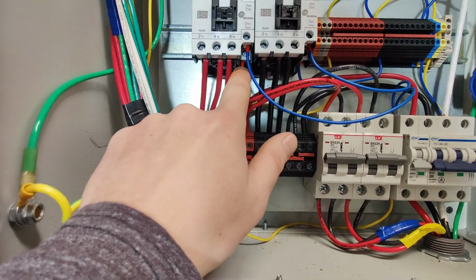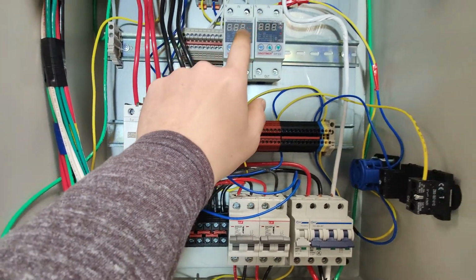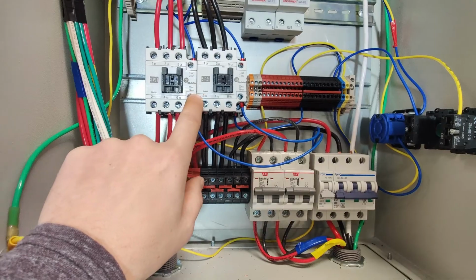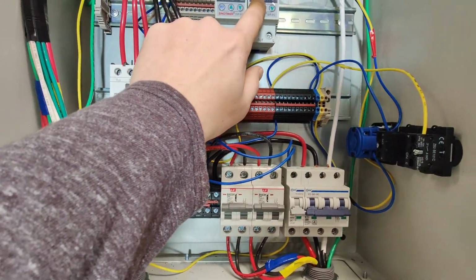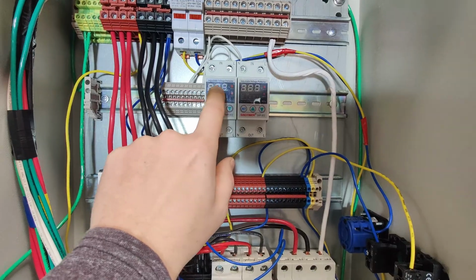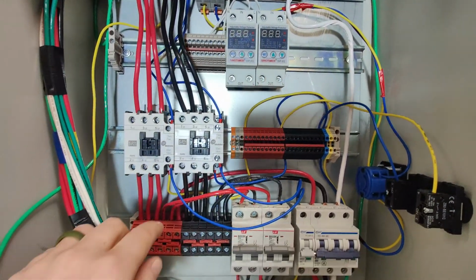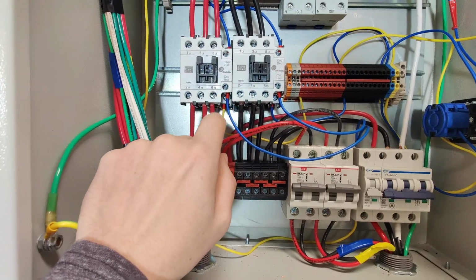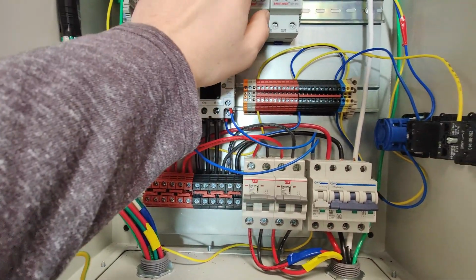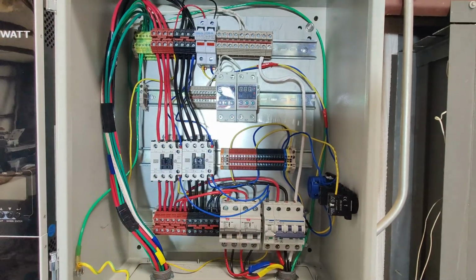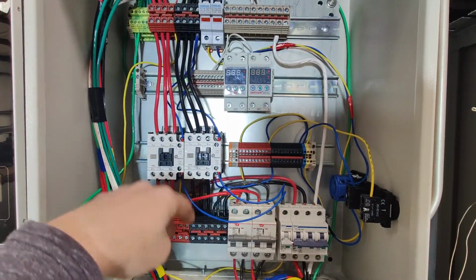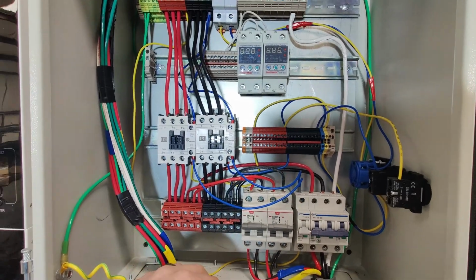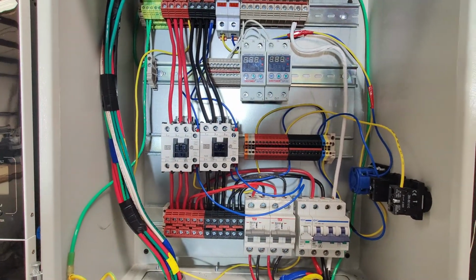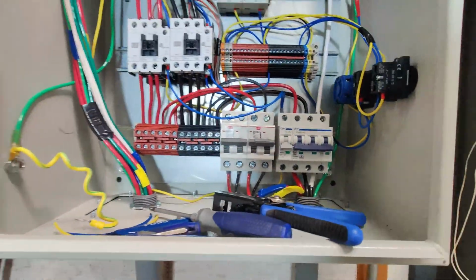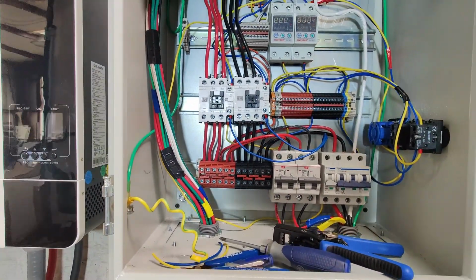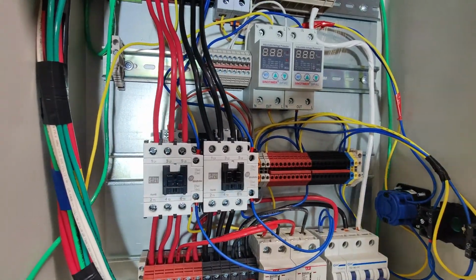And the reason that we need to do that is we don't want to start measuring the voltage up here until this contactor is closed. If we start measuring the voltage up here, we'll get these weird readings on it. It won't work correctly, so we're wiring this into the normally open side of the contactor, so that way we don't even start measuring voltage up here until it's ready to start being measured, because it's got something into the auto transformers. So I just wanted to show you that real quick. Okay, and now the wiring is complete for our whole system. So let's go through what's going on here.